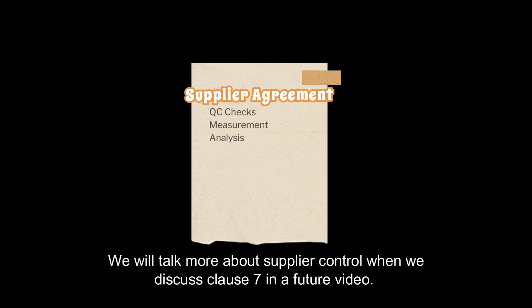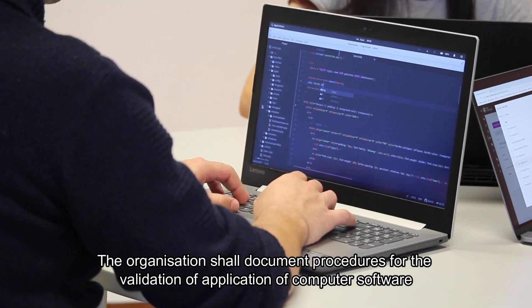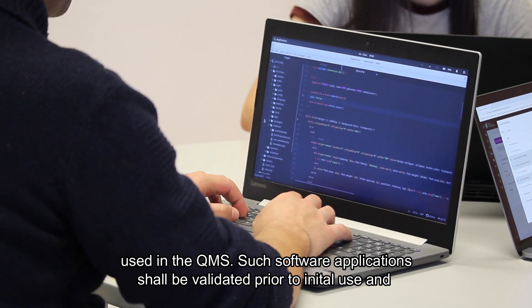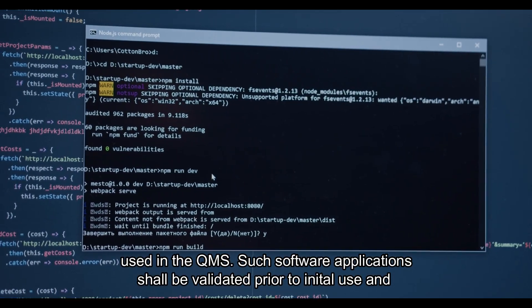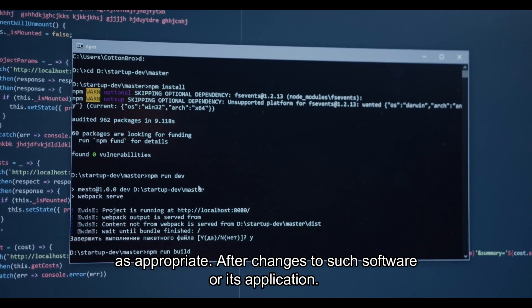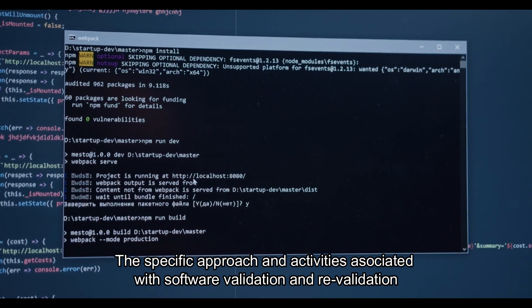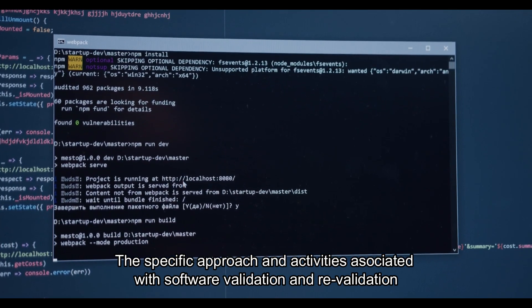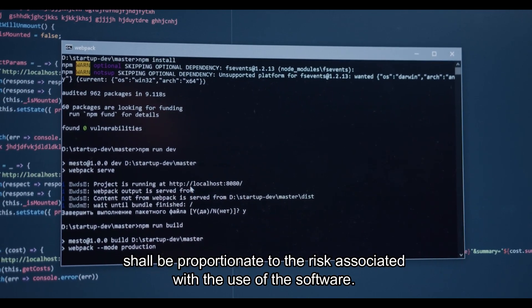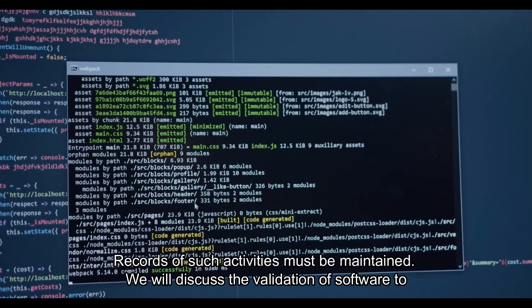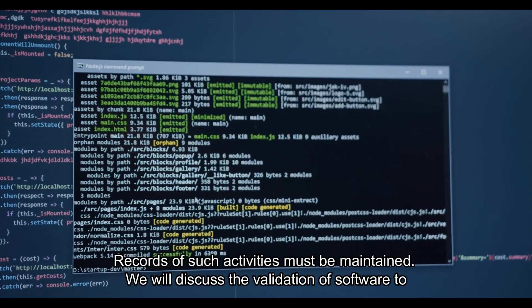We'll talk more about supplier controls when we discuss Clause 7 in a future video. The organisation shall document procedures for the validation of application of computer software used in a quality management system. Such software application shall be validated prior to initial use and as appropriate after changes to such software or its application. The specific approach and activities associated with software validation shall be proportionate to the risk associated with the use of the software. Records of such activities must be maintained.